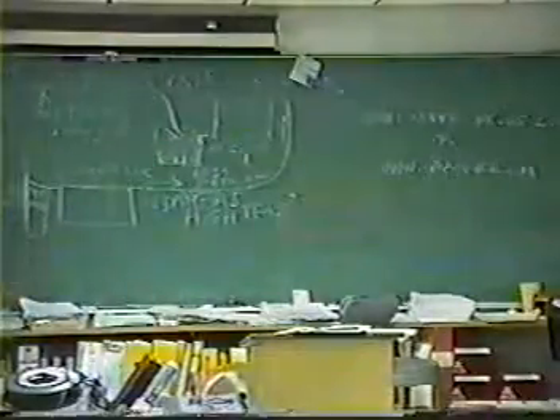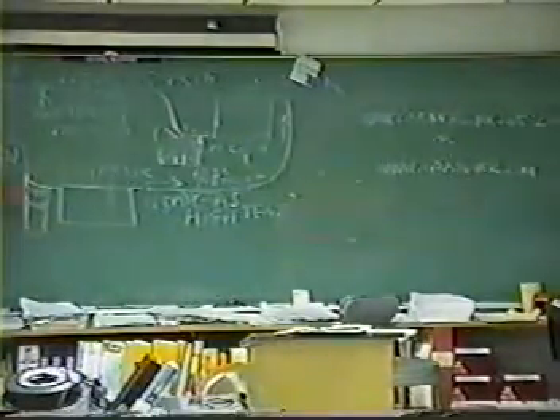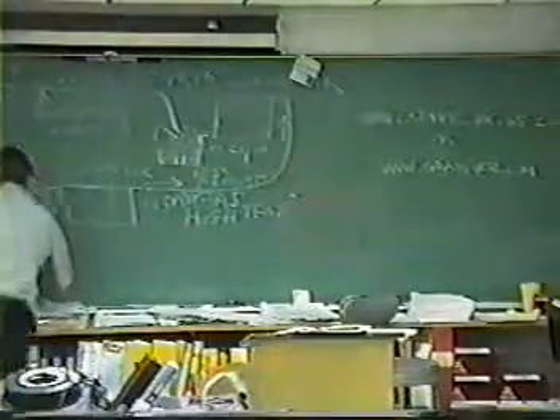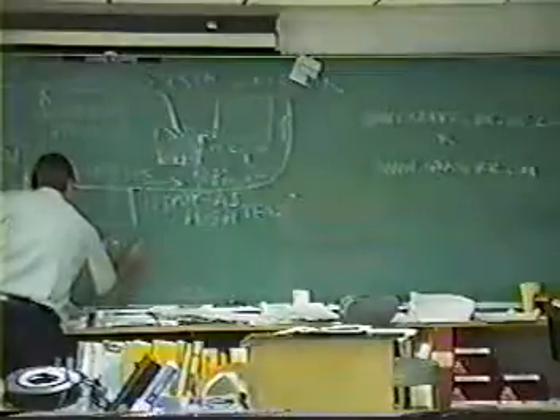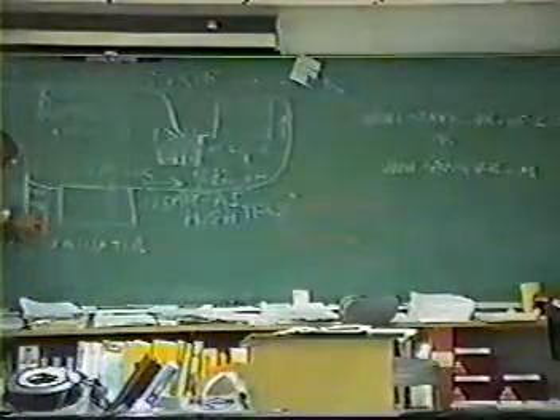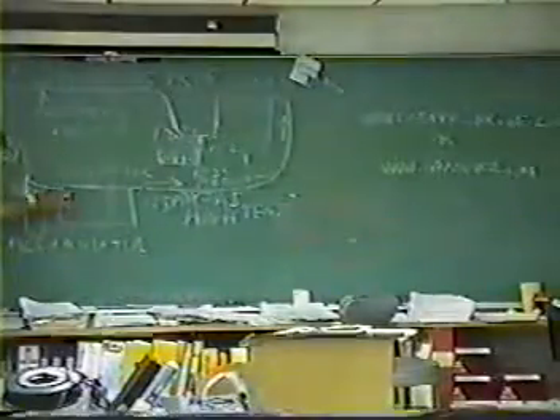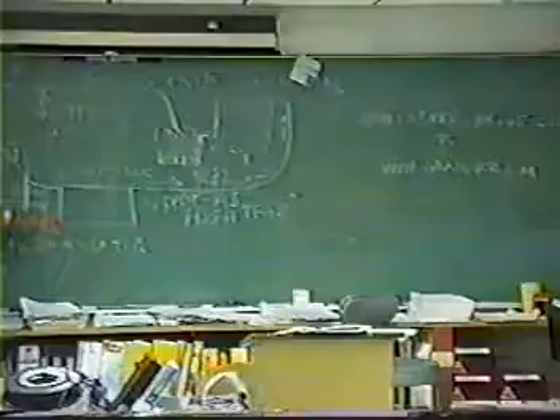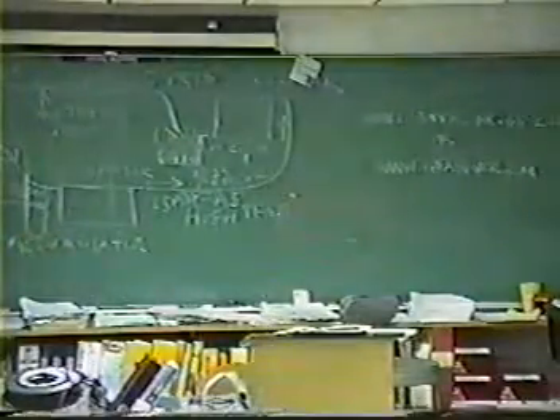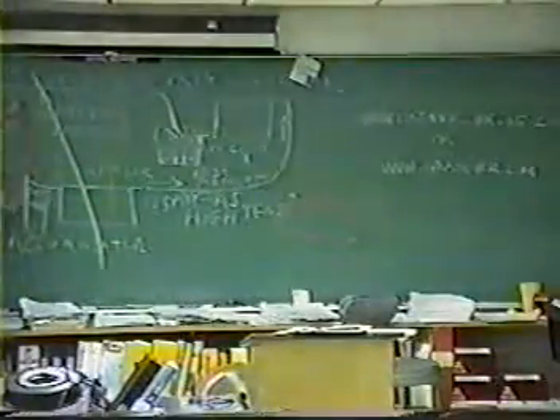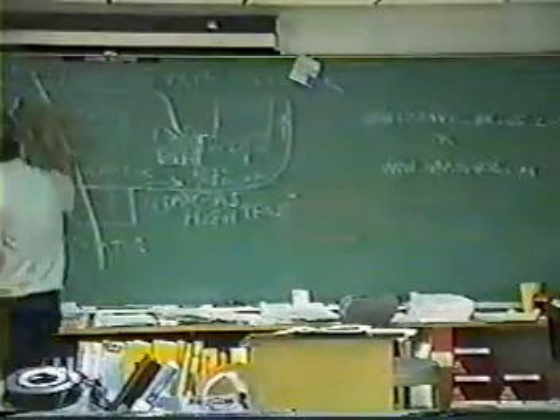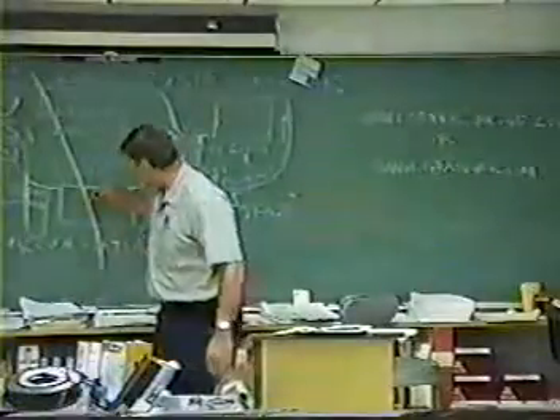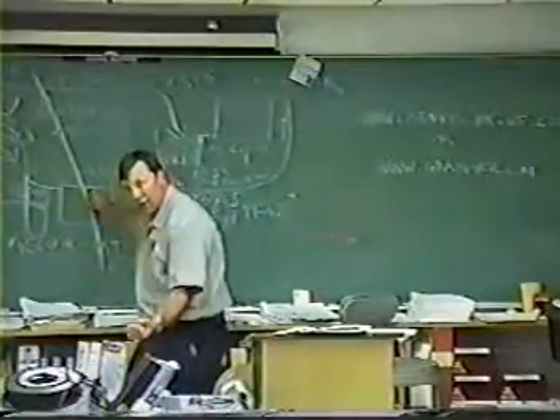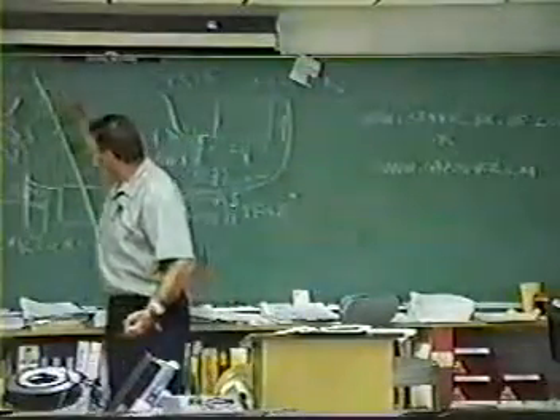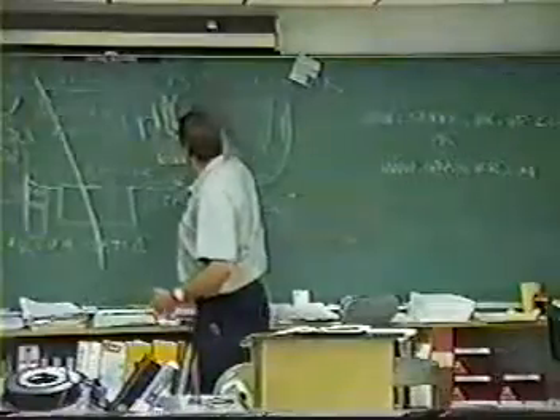And any liquid that might be coming from this evaporator going to this accumulator will come in here and boil off, and the vapor is always going to that compressor, so it won't destroy that compressor. Low pressure, because from here on back you've got low pressure. Low pressure is from your metering device to that compressor, which brings it in as low pressure and compresses it to a high pressure. This whole side is low pressure, this side over here is high pressure.